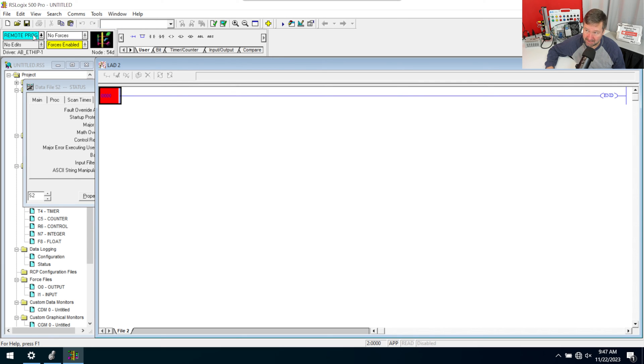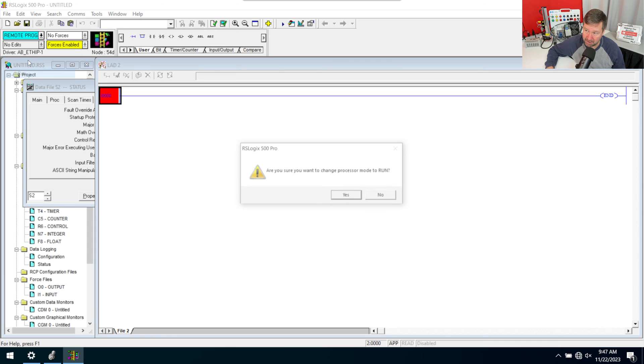...and then we download that program. Right now we're in remote program because I cleared the fault and put it into remote program. When I try to go to run, it's going to fault. And that's where we get error code 28. So the PLC has to see this ladder 3 routine. Since you don't have it in your list, that is going to fault this PLC immediately.